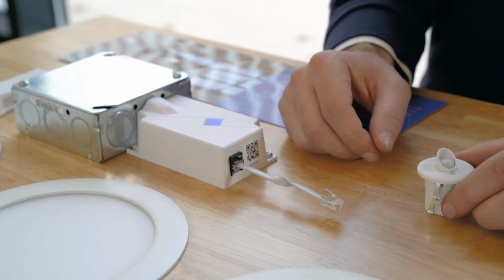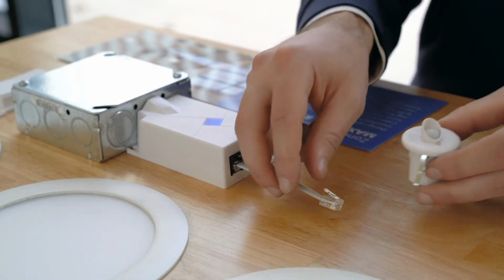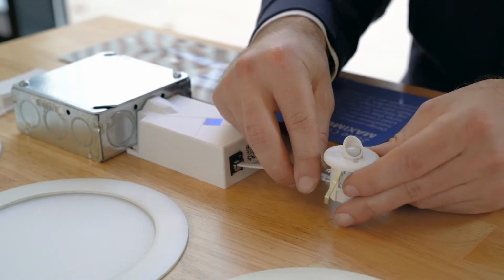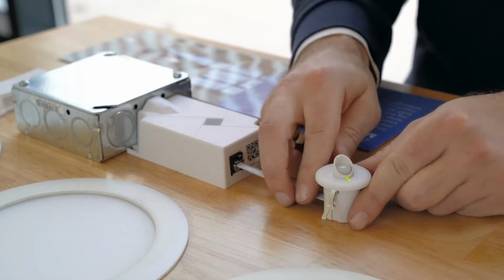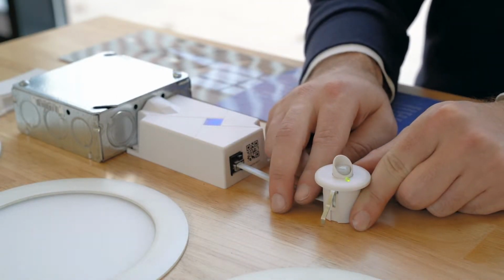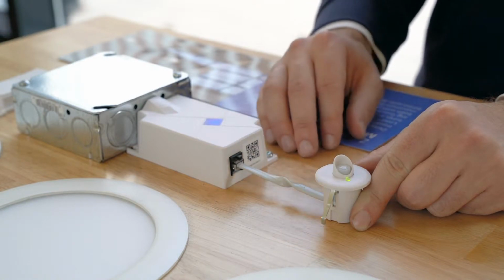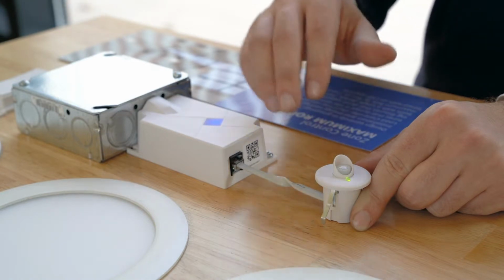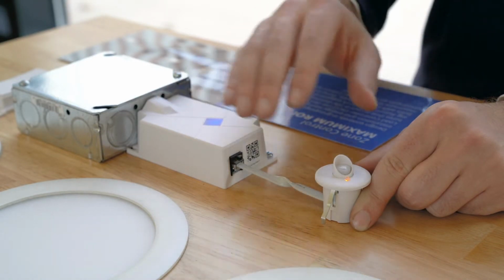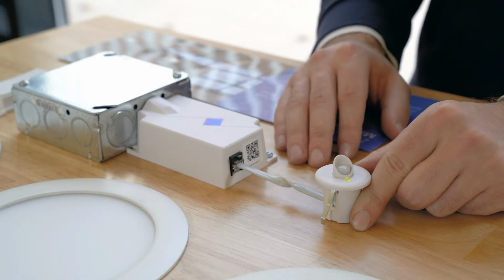Next to the PIR sensor, you'll notice an LED bulb which indicates occupancy detection. This bulb can be used to help optimize sensor placement after the system is powered on. When the sensor is powered and does not detect motion, the light is green. When motion is detected, this light turns orange. You can use this feedback mechanism to confirm occupancy detection where you want it and not where you don't.